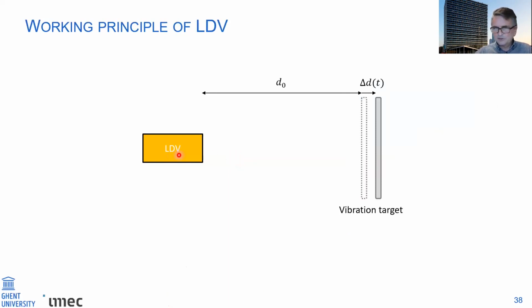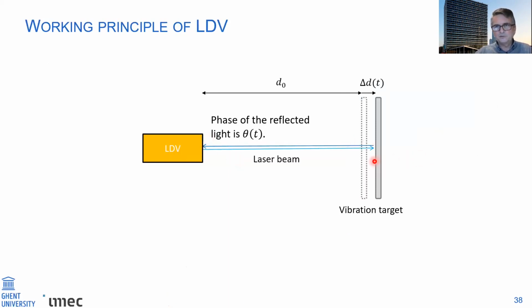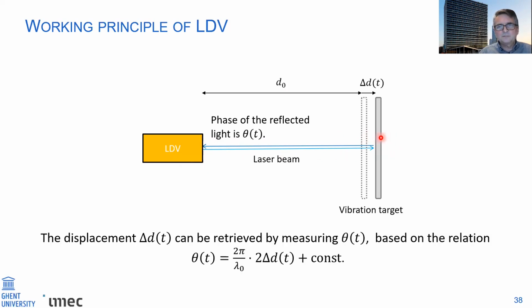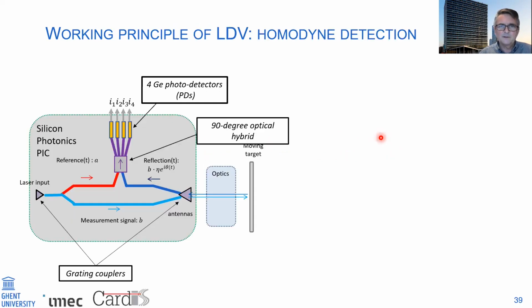In laser Doppler vibrometry, you send a laser beam to a target, and the reflected light is coupled back to the same device. And then with an interferometric technique, you measure the optical path length of this distance between device and the target, in this case, the skin of the patient. And of course, when this moves around, you will typically have a change of that optical path length, which leads to a phase change, which you can detect.